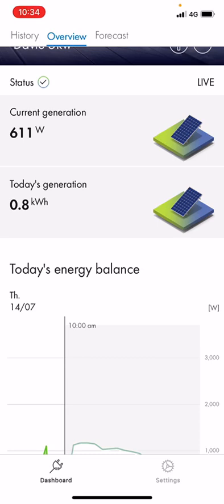Underneath is today's generation. When focusing on whether your system is doing what it should, I push customers to look at today's generation. When we sell the system to you, we give you a panel report — on page two you'll see a generation table of your average daily generation across each month, which gives you an idea of what to expect in terms of output. On an overcast day like today your system will be down, but if it clears, the system can push up to four or even five kilowatts pretty quickly. This is a five kilowatt inverter. Today's generation gives you a better reflection than current generation.